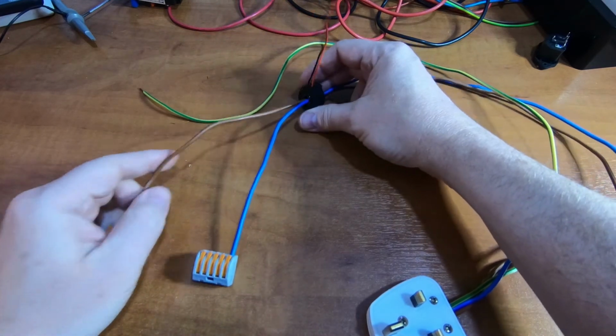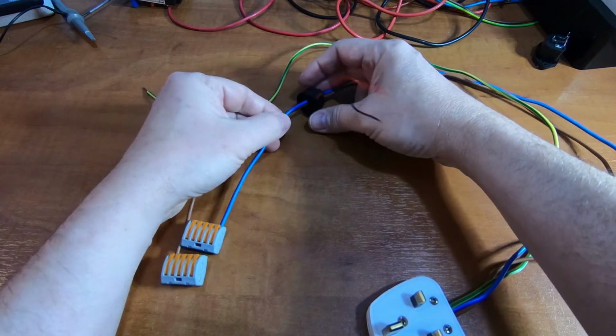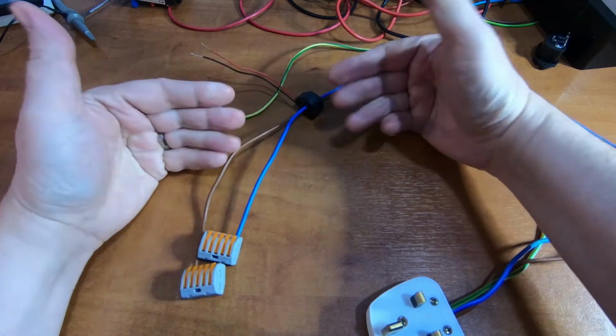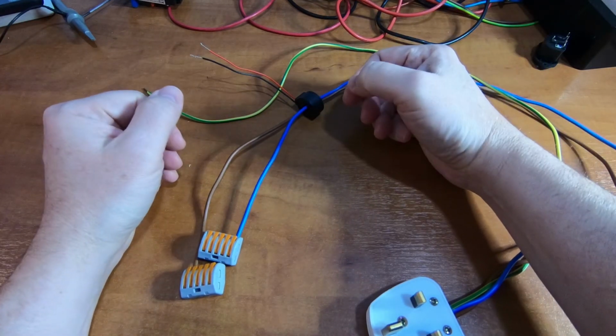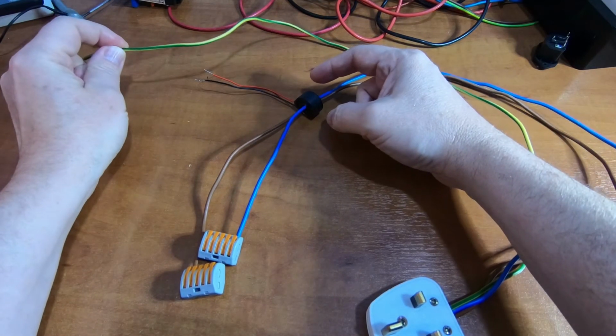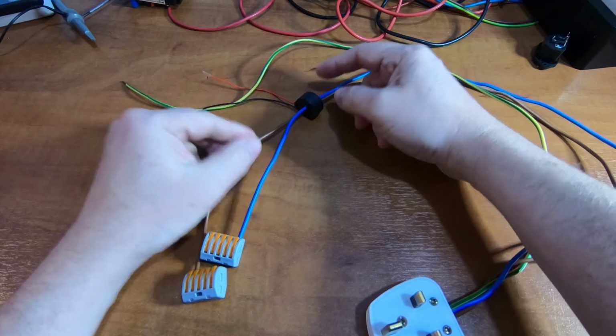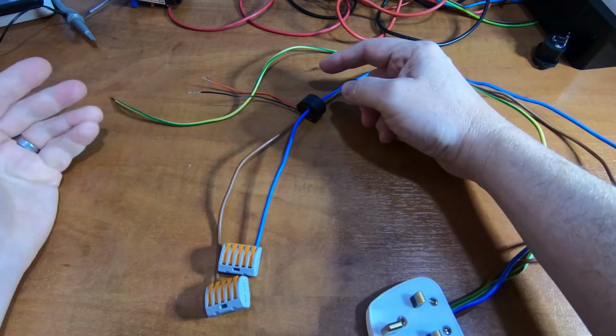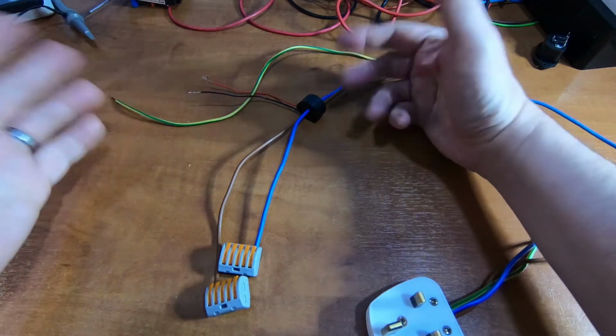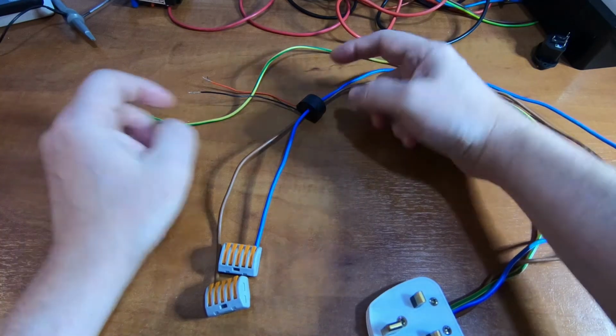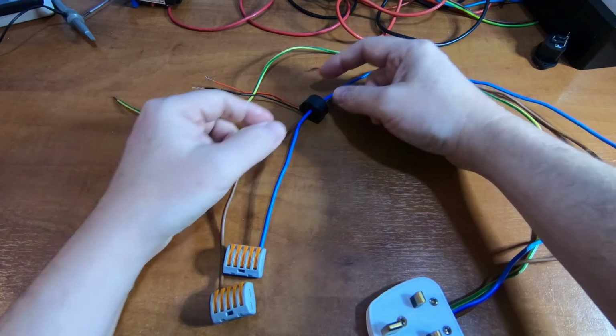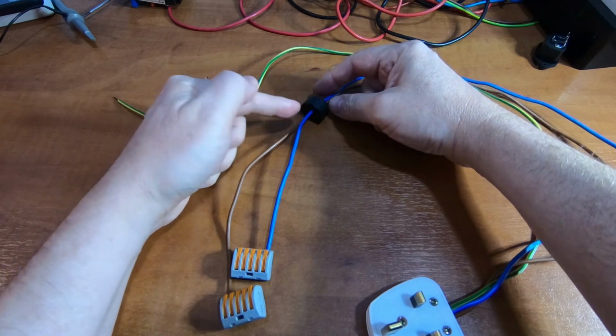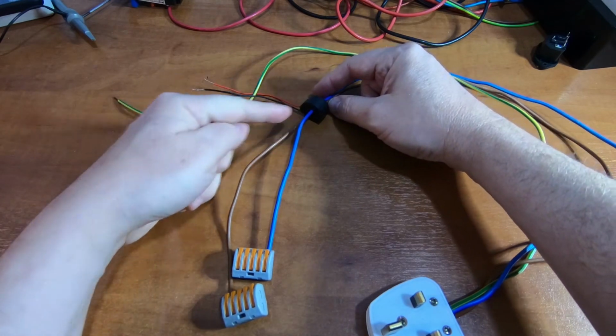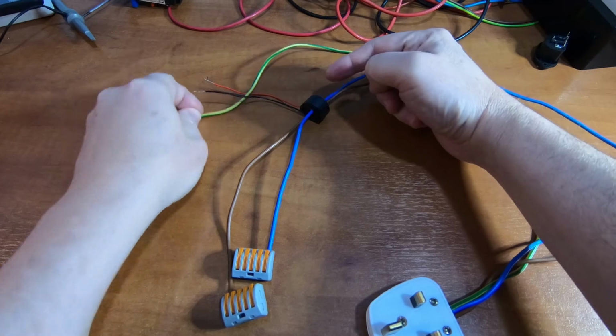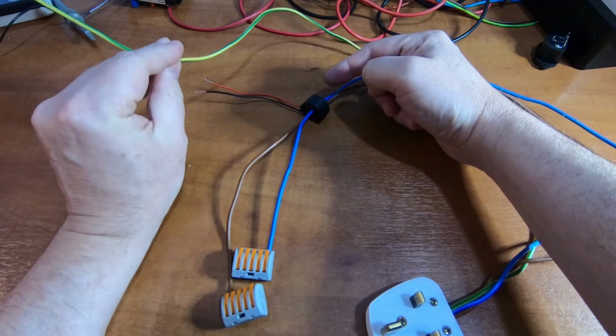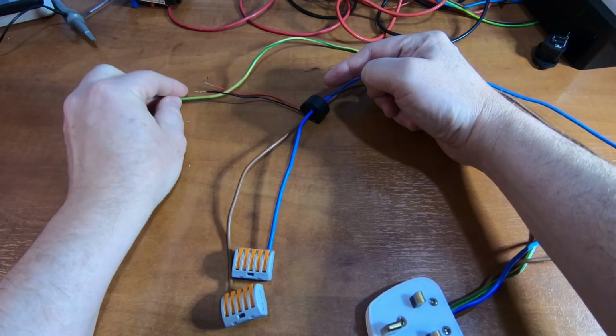What's going to happen here is the earth and neutral come past my current transformer - this is how it's going to be in my test box, with the earth leads separate. That way any current that comes back through the earth leakage is not picked up by this current transformer, and therefore it will show the difference between what's returning on the neutral and what isn't, essentially what's coming back through this earth lead.